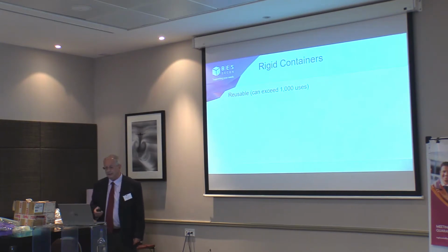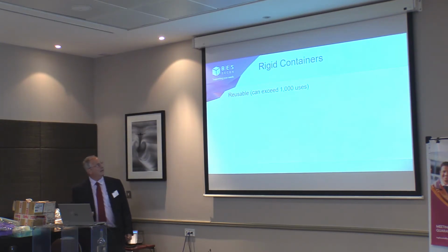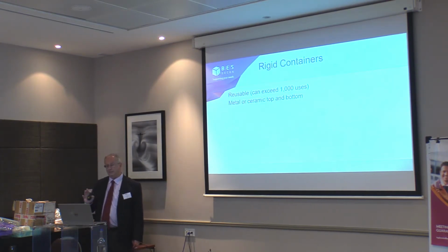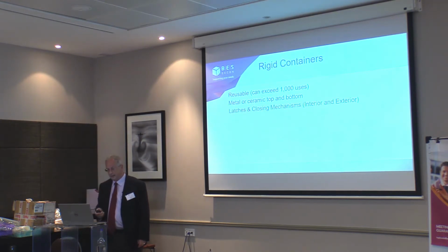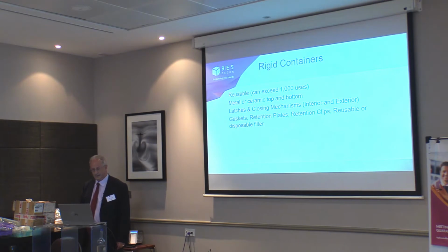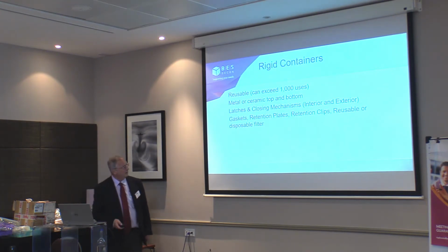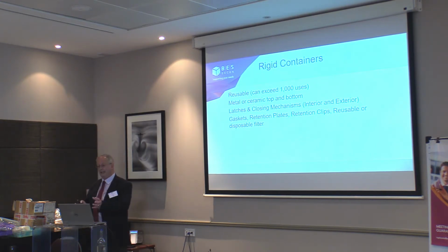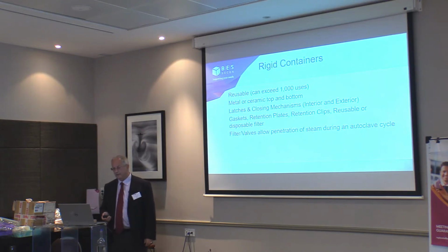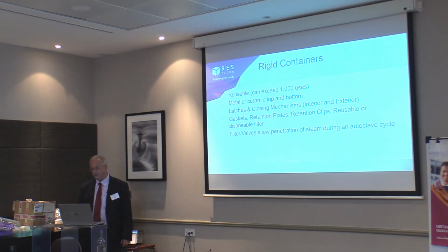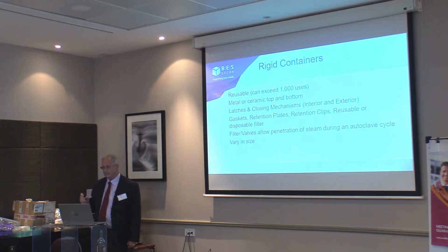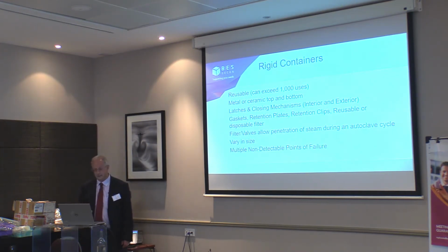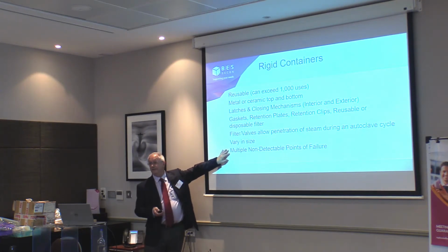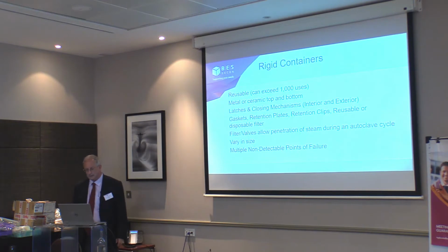So, quickly looking at reusable containers. Reusable means that they can exceed 1,000 uses. They're made of metal or ceramic materials, top and bottom. They've got latches and closing mechanisms, interior and exterior. They've got gaskets, retention plates, retention clips, filters and so forth. There are lots of bits that have got things around them that can go wrong. And the filter and valves allow penetration of steam during an autoclave cycle, which is good. But these varying-in-size filters don't always work, and there's no way of testing whether they're working or not. So you get multiple non-detectable points of failure. And that's the critical thing really in the system. They're non-detectable. So is this a real issue or not? We'll have a look at that in a moment.